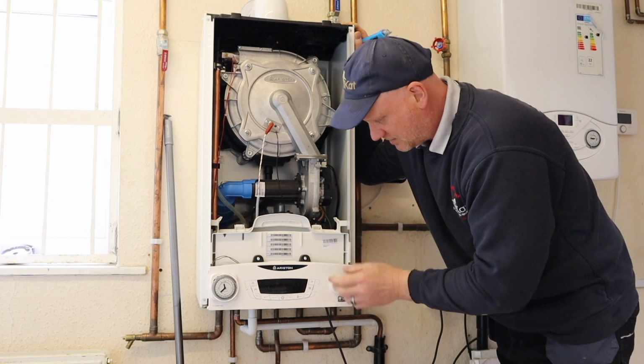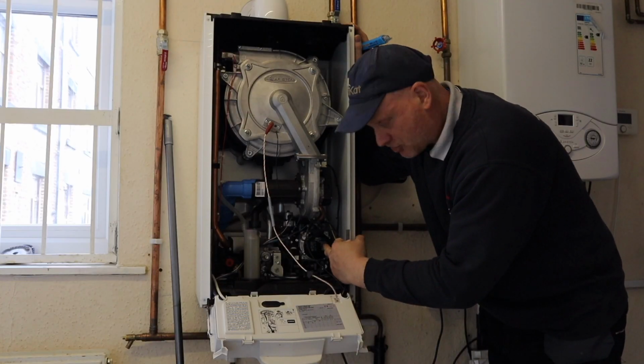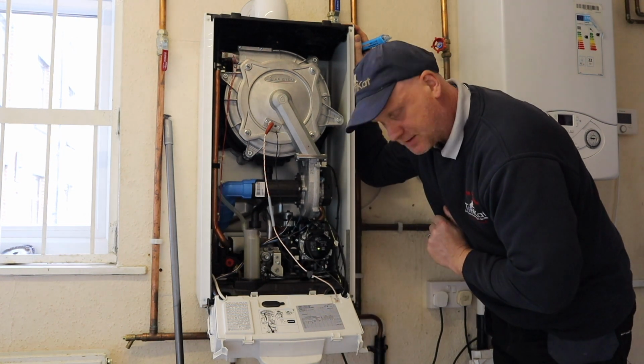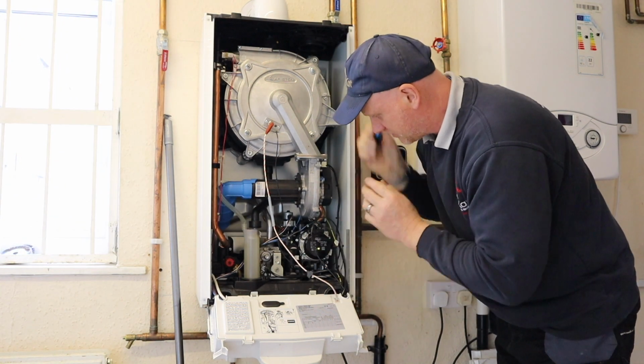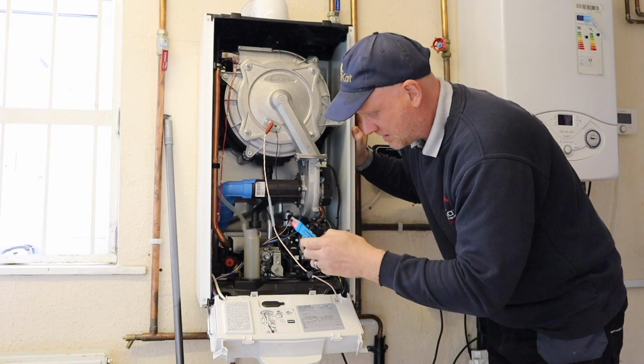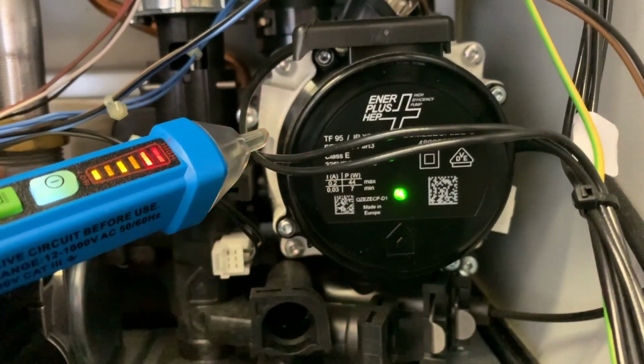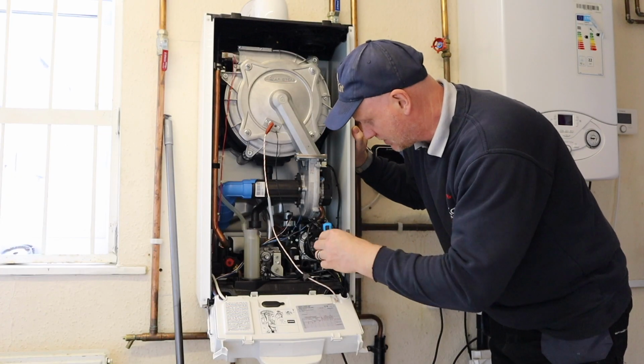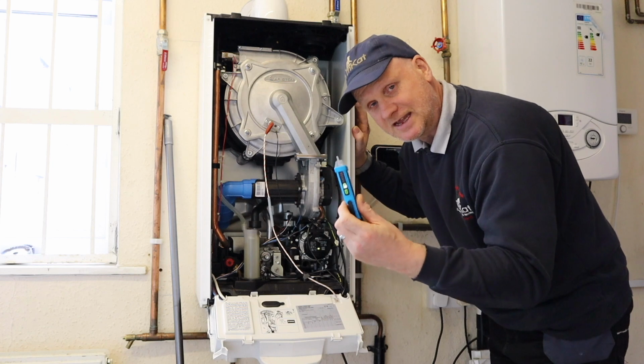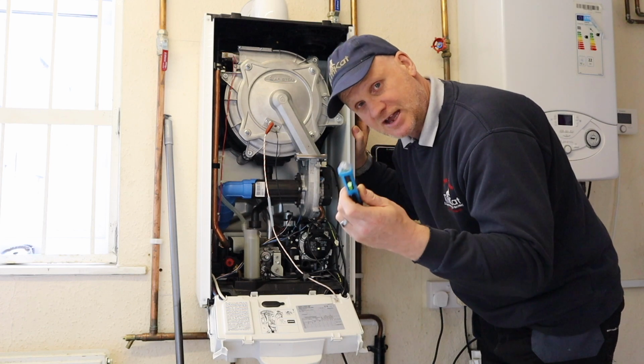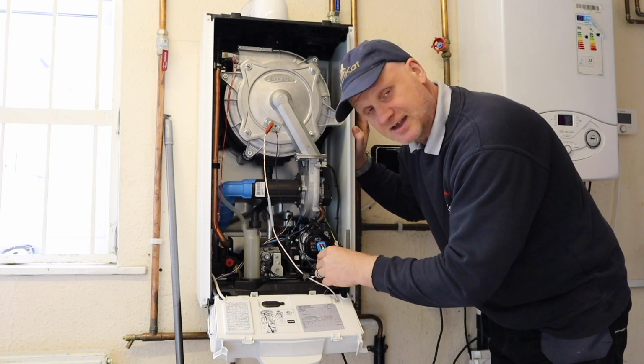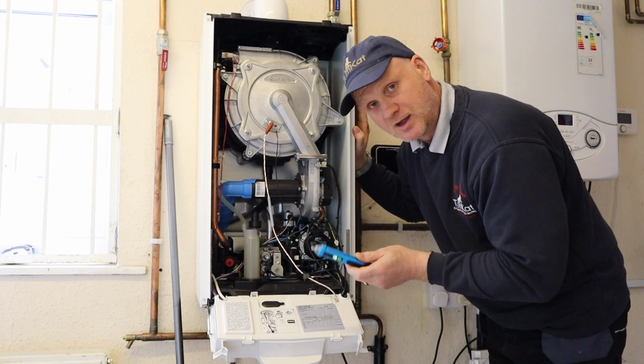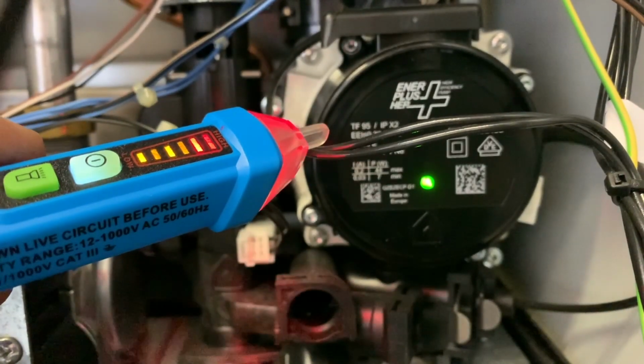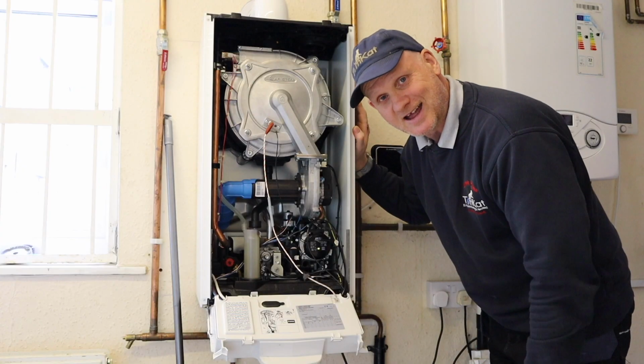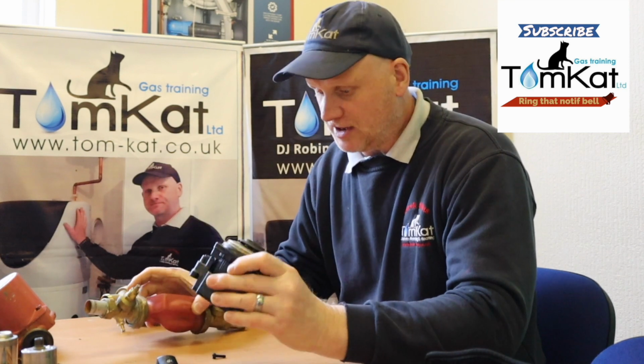Now if I turn this boiler on, so what will happen now is a green light will come on the pump here and tell us the pump is actually running. But if it hasn't got that green light, we can actually use our non-contact voltage indicator to tell us that there is power actually going to the pump. Now we shouldn't be using these as a way of checking if anything's dead, but we can check and see that there is voltage going to this pump. So we know we've got 230 volts going to that pump, but it's also got a green light there to show us that it's working. And that's a look at what's inside central heating pumps.